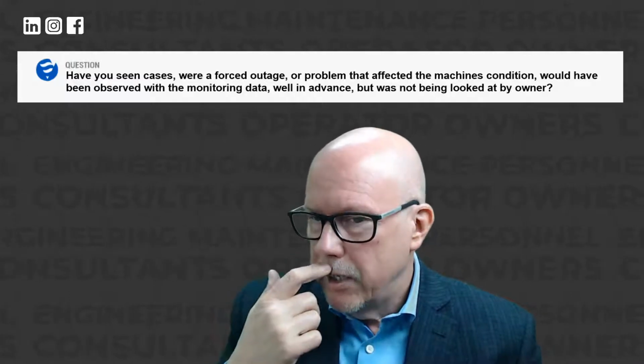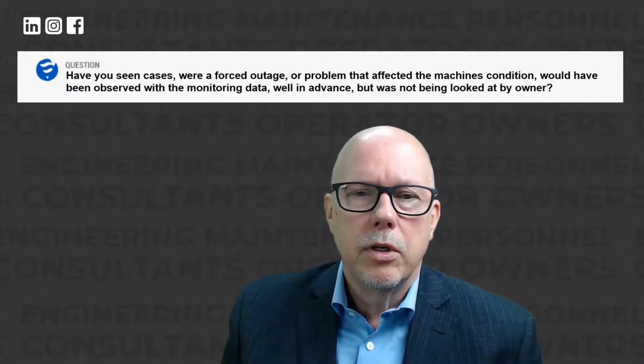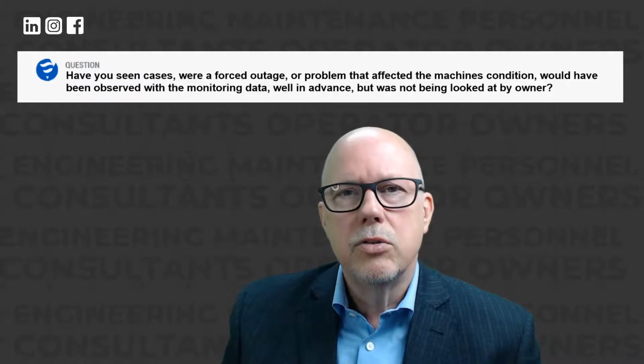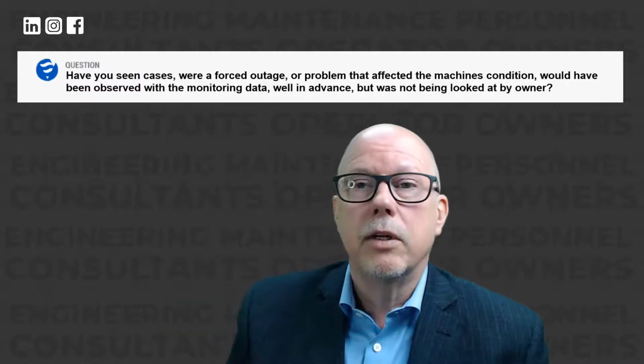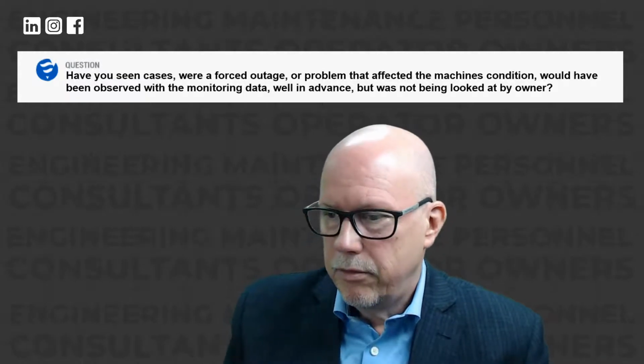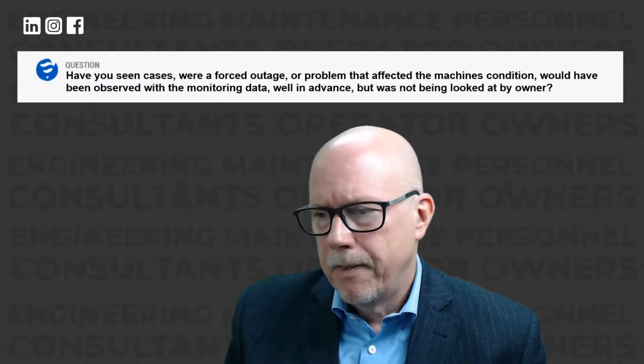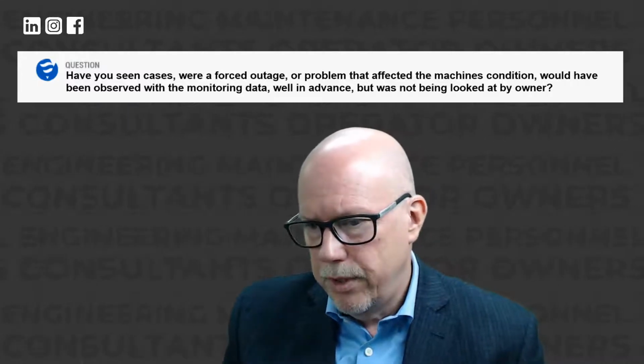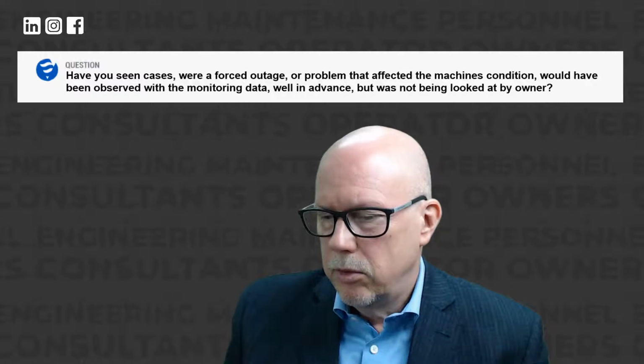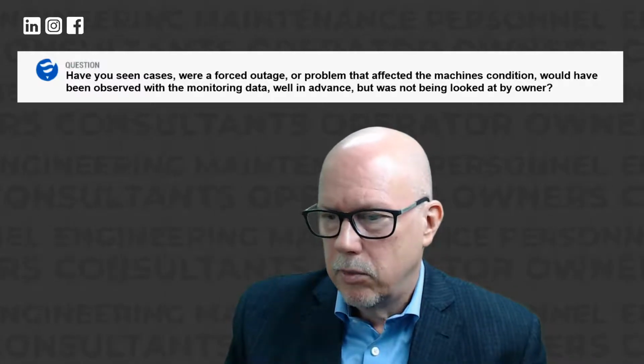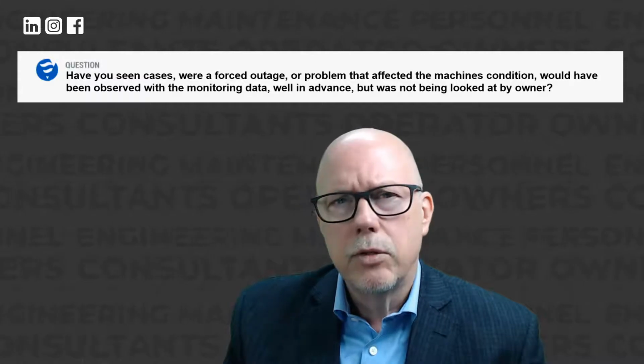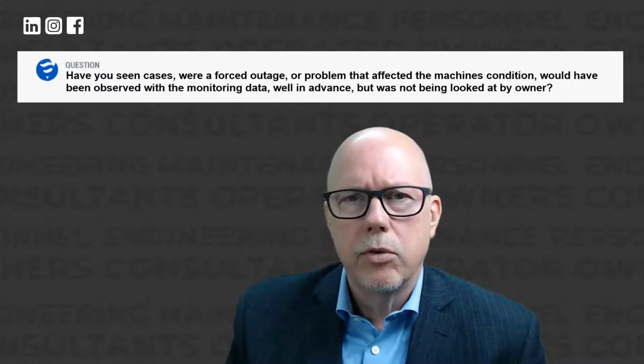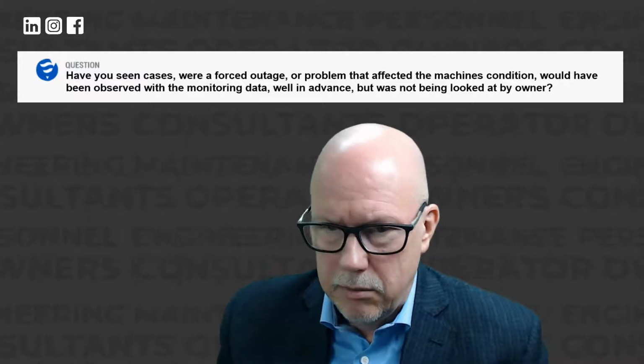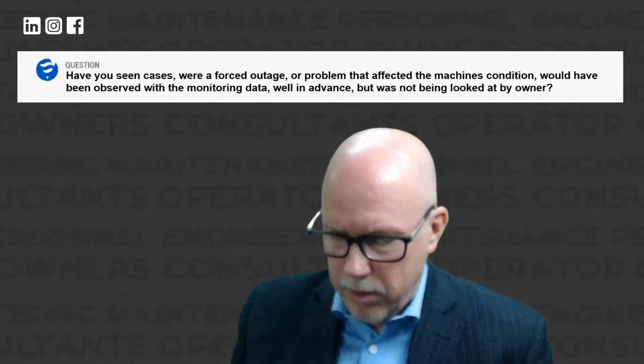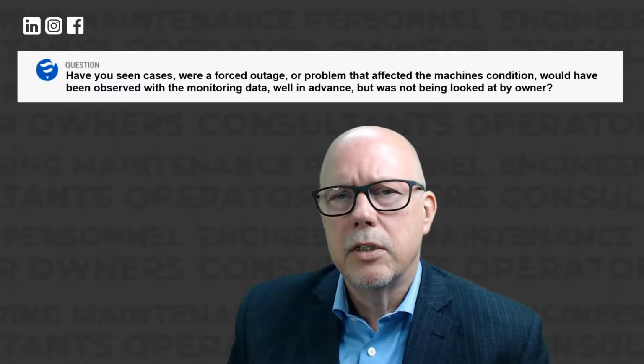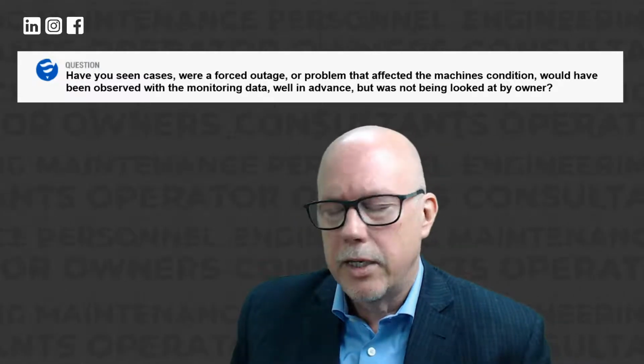So yes, there are quite a few cases where issues were raised, observed and analyzed using data that the customer was completely unaware of and totally surprised by. We've helped quite a few utilities either enforce warranty issues or stop a unit and prevent failure. We had a case a few weeks ago in Latin America where the customer used the data from our report to stop a unit because they were very close to having a rotor stator rub. And they're using the information from our reports and from our Tests and Diagnostics department to help them fix the issue. So yes, we do have quite a few cases like that.